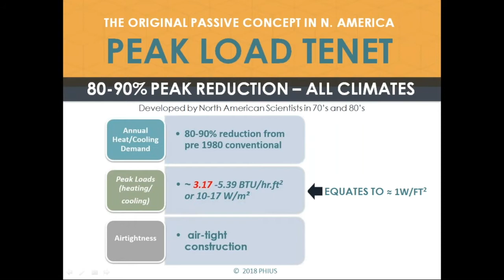Basically, the equivalent to the 10 watts per square meter that the PHI picked up on and ran with. And here in the US, 1 watt per square foot. But the general structure here of how to go about the design process: take care of the envelope first and set a target in terms of reduction, then take care of the loads, reduce them as much as you can to minimize the mechanical system, and then have airtight construction to provide durability and prevent any kind of moisture failure. So I just noticed that this title right here, I forgot to change.